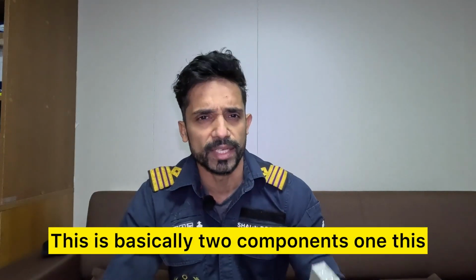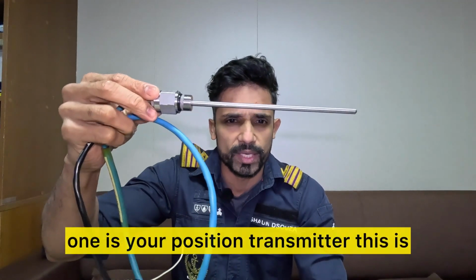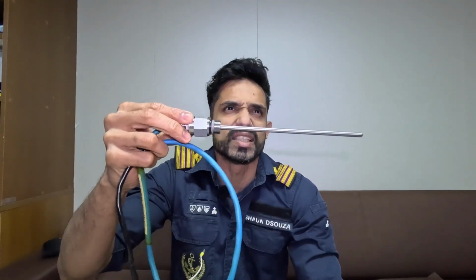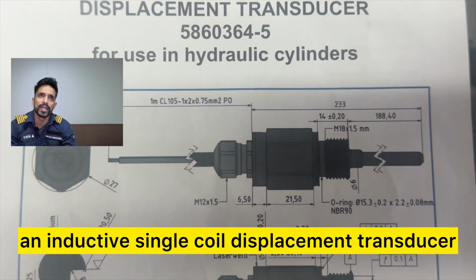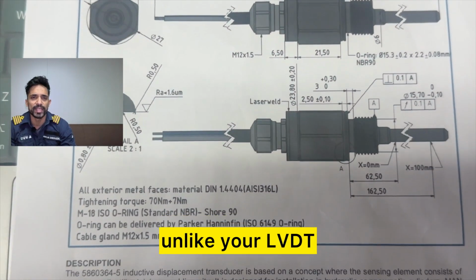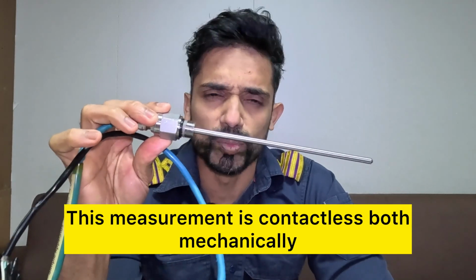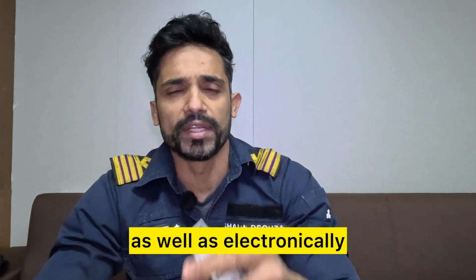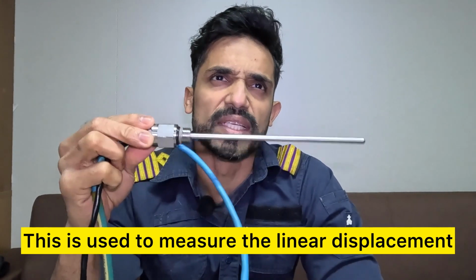This is basically two components. This one is your position transmitter, an inductive single coil displacement transducer, unlike your LVDT which has two coils. This measurement is contactless, both mechanically and electronically, and is used to measure linear displacement.